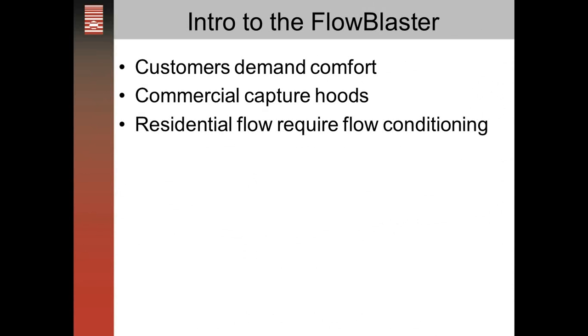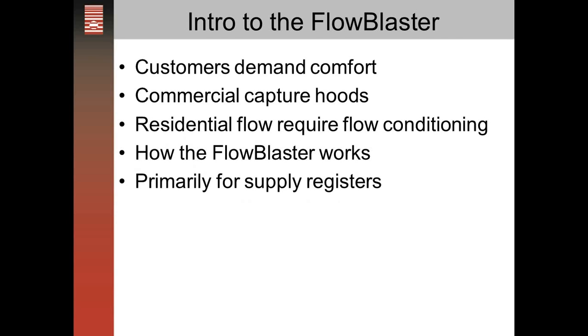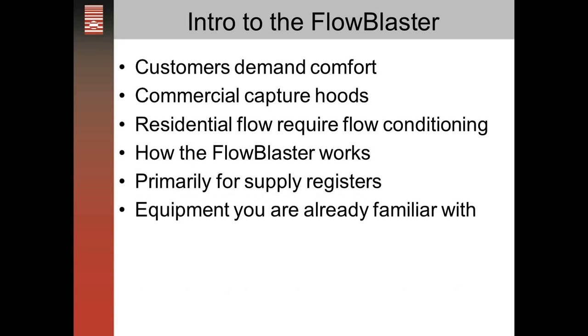Flow conditioning is needed to smooth out the flow, but the flow conditioning adds resistance which changes the flow measurement. This is especially true with lower airflow measurements. So the Flow Blaster works by adding the necessary flow conditioning and then precisely adjusting the duct blaster fan to compensate for the pressure losses. It's designed primarily for residential supply registers, although it can also be used to measure return flow or exhaust fan flow. An advantage to the Flow Blaster is it uses equipment you're already familiar with.